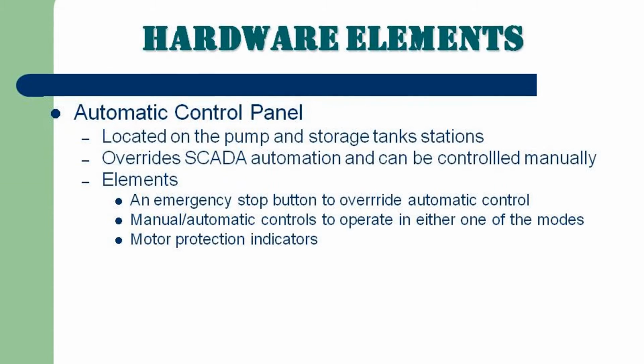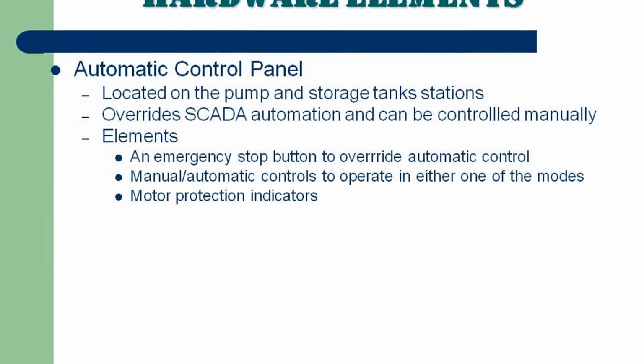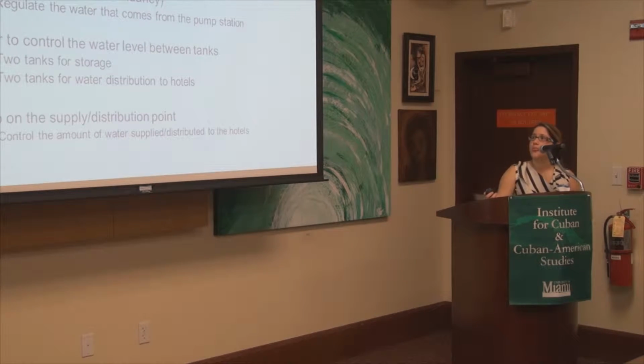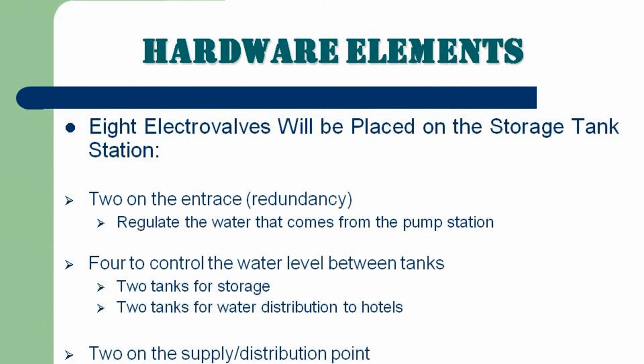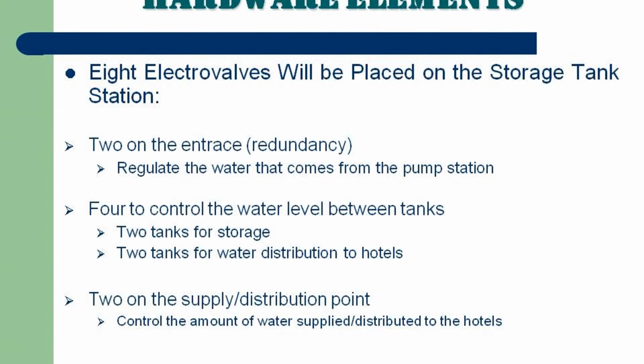Besides the RT units, we're going to have an automatic control panel. This is very important. It is located at the pump and storage tank station. It overrides the SCADA automation. If the system were to fail, you can manually stop it and run it again if necessary. The elements are an emergency button, a manual automatic control, and a motor protection indicator for the pumps. There are going to be 8 electrovalves placed in the storage tank station, 2 at the entrance to monitor the water that is coming from the pump station, 4 to control the water levels at the tanks, and 2 at the supply or distribution points to the hotels to see how much water the hotels are consuming or how much water you are supplying to them.